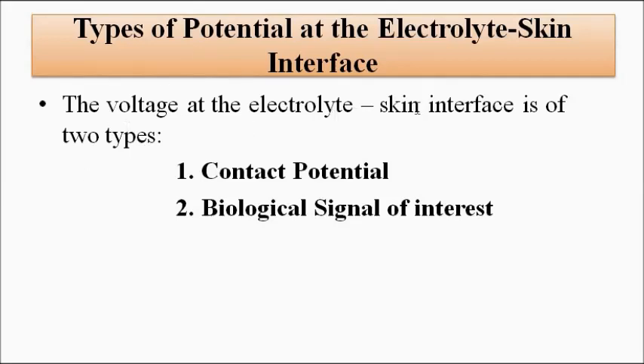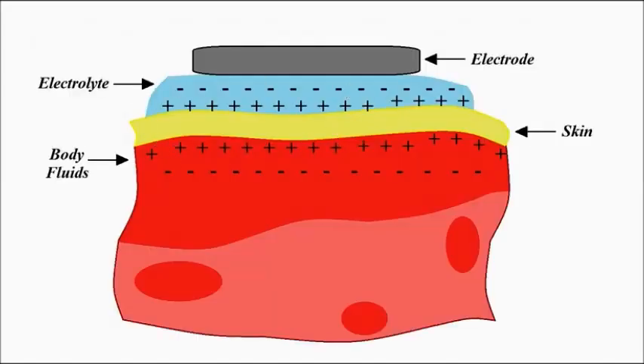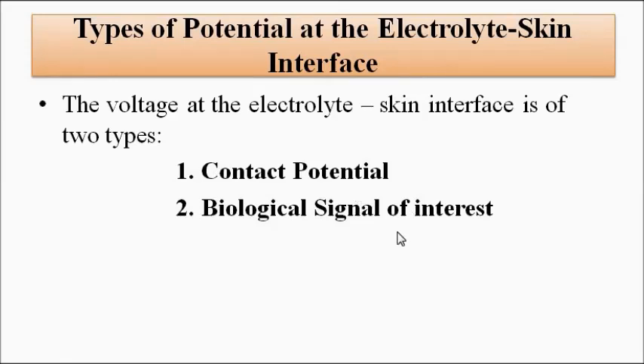The voltage at the electrolyte-skin interface presents two signals to the electrode. One is the contact potential — the electric potential of non-physiological origin because of this charge separation. The second is the biomedical signal of interest, be it ECG, EEG, EMG, or any type of signal we want to measure. If the contact potential value is high, it can mask the original biological signal of interest. Our objective is to keep this contact potential at a low value, and proper signal conditioning and processing is required to remove it.